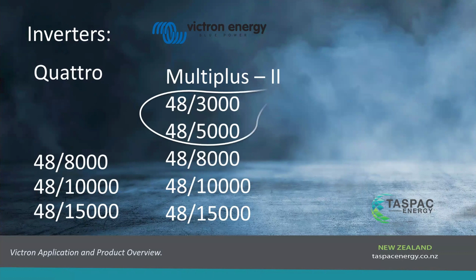Okay, so if we look at what can be paralleled, the Multiplus 3000, 5000s can, the 8, 10, or 15s not yet, and it's unlikely they're saying that they will be able to be paralleled, mainly due to limitations in the electronics inside the inverter. The Quattros, yes, you can parallel those. So you can get up to 180 kVA three-phase by using multiple 15 kVA Quattros on each phase. So it's a pretty big, pretty decent system.